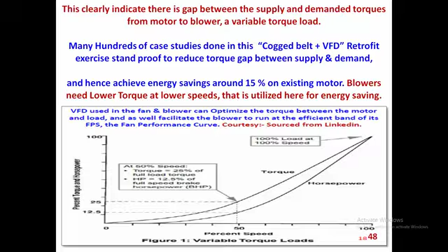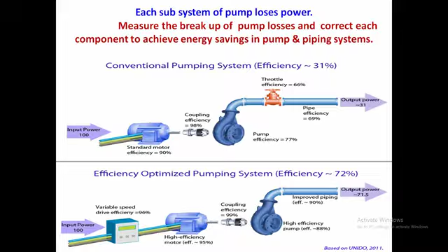In the case of pumps, around 70-80% is possible, whereas the old system efficiency is around 31% and the new efficiency is around 70%. You can see the difference. The difference comes not only at the motor end, but at the coupling, at the pumps and at the throttling efficiency, everywhere. Ultimately, 40% scope is there, especially in the replacement of pumps and piping systems. We don't say the pipes must be replaced, but see to it that the efficiency can be improved here.